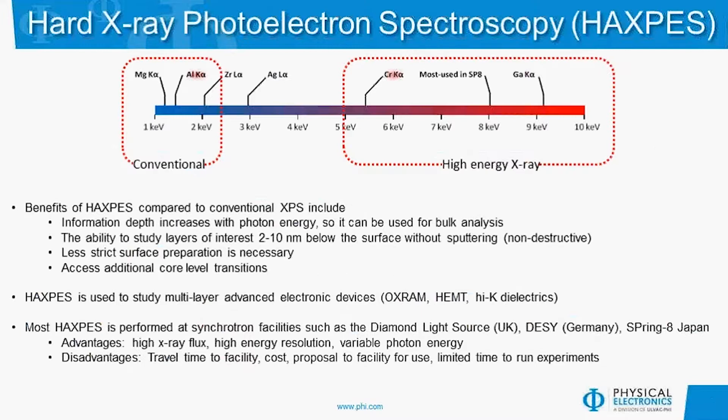In general, photon energies of 2 keV and below are considered conventional XPS, which would include magnesium, aluminum, and zirconium X-ray sources. Hard X-ray photoelectron spectroscopy, or HAXPES, covers photon energy ranges between 5 and 10 keV, which would include chromium and gallium X-ray sources. When the photon energy is increased, so does the information depth, so HAXPES can be used for more bulk analysis.